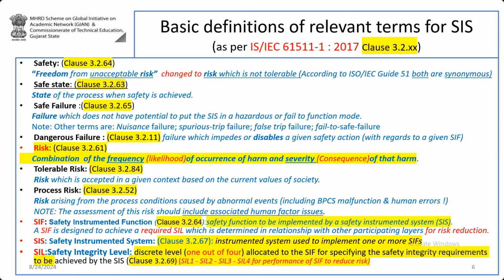So such a type of failure is known as a nuisance failure. Such nuisance failure is not always welcome because you'll be losing the production. The plant is getting shut down just like that, and you don't know the reason why it is getting shut down. One has to analyze the reasons of the safe failure as well.